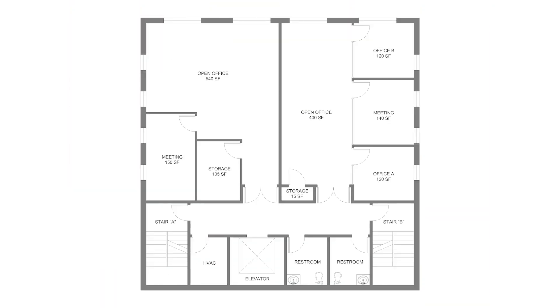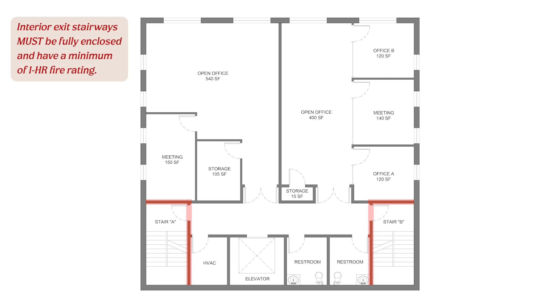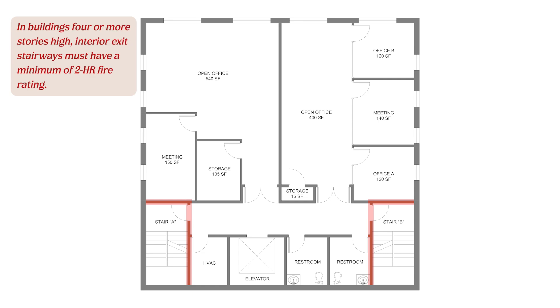Let's look at a floor plan and discuss which walls must be fire rated. Exits like fire stairs are protected spaces to allow for safe means of egress, which means those walls most definitely need to be fire rated. Vertical shafts provide the most direct path for fire and smoke to spread from floor to floor, so interior exit stairways must be completely enclosed and have a minimum of a one hour fire rating. In buildings four or more stories high, interior exit stairways must have a two hour fire rating.